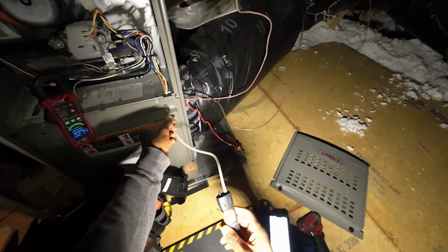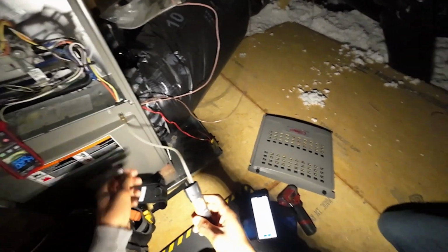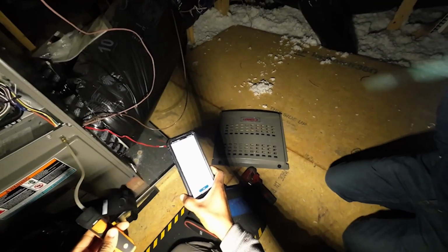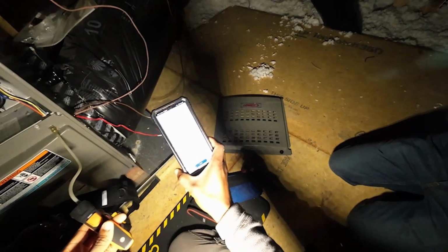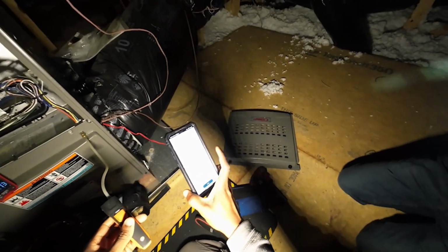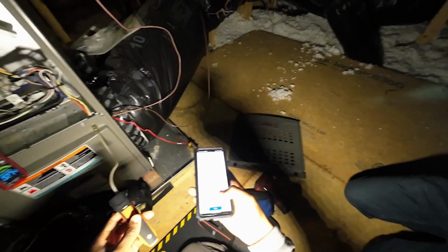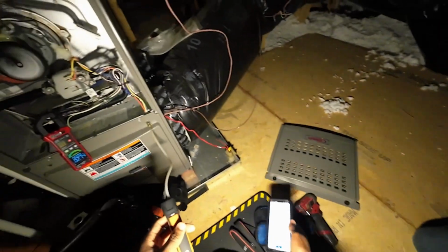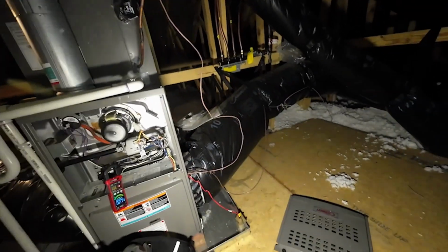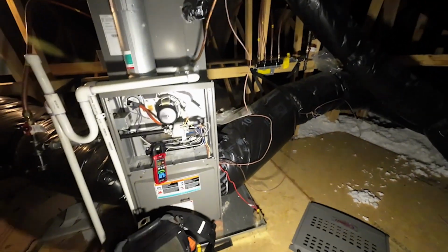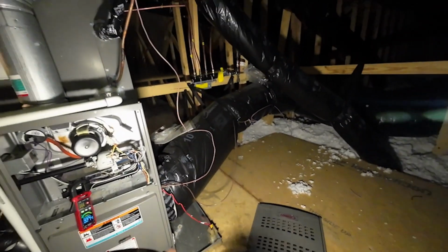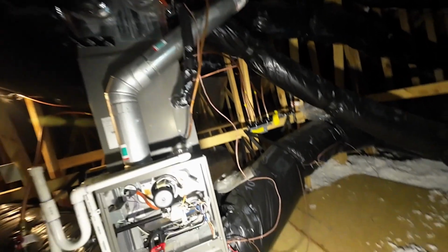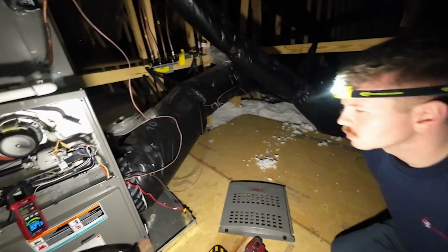Now I'm going into a negative pressure zone. See that? So you've got 0.12 inches of water column negative. See the minus there? Mm-hmm. I'm just going to go ahead and push that. It'll capture that value. Now if I want to check my positive pressure, if you want total static pressure, this is important to capture. Total static pressure is going to be, let's think of a way to explain it. Static pressure is everything that's creating resistance of flow on this motor.